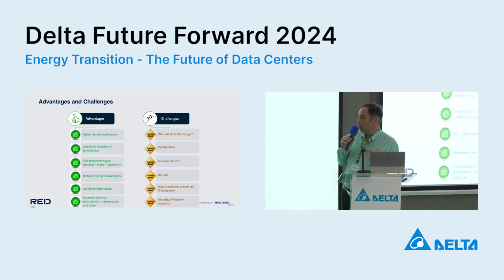Although this doesn't particularly talk about AI, when you look at the higher loads of 150 to 200 kilowatts a rack, as opposed to the 10 to 20 you might typically design for at the moment, you start looking at a lot bigger electrical infrastructure to serve your building and a lot more IT infrastructure. That means in an AI building, it doesn't get smaller, it stays about the same size. Your floor to ceilings go from about 7 metres clear to 9.5 metres clear to allow for all the infrastructure over the top of your racks. So there's a lot of balancing to be done.